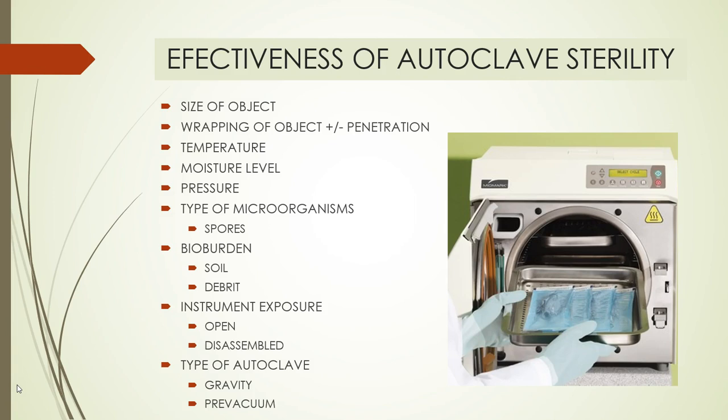The effectiveness of autoclaves and the use of autoclaves depends on many things. How you wrap the instrumentation is of course important, and the autoclaves must be properly functioning. Again, it is critical that these objects be cleaned before being placed in the autoclave, and things that have hinges and little screws and have multiple components, these things must be properly scrubbed and cleaned before placing them in the autoclave. There are, of course, different types of autoclaves that are available. The critical issue, again, is proper use, proper maintenance of the autoclave, and making sure the instruments have been cleaned before proceeding with autoclave use.